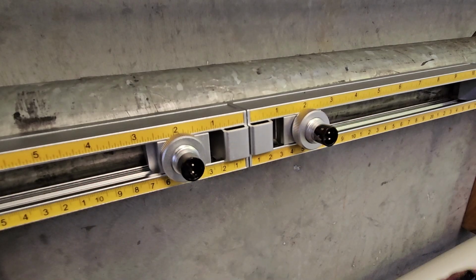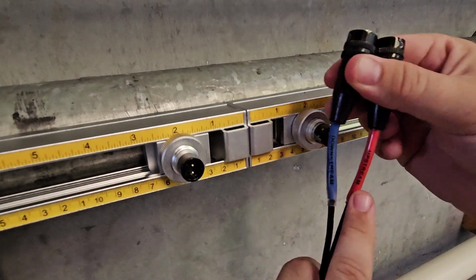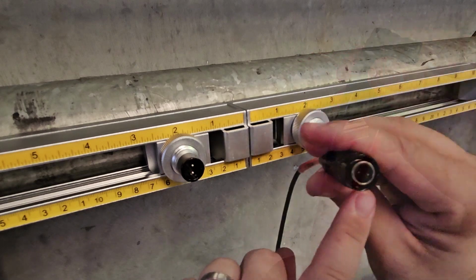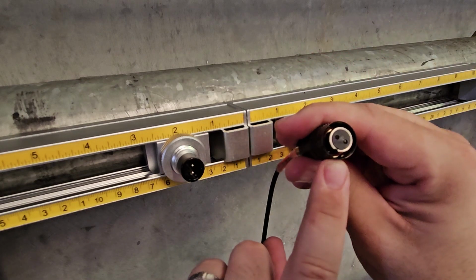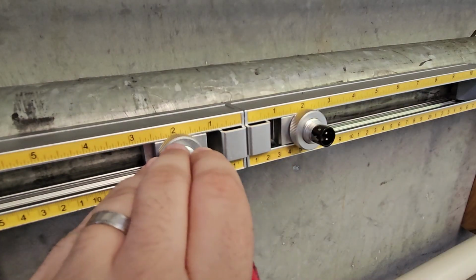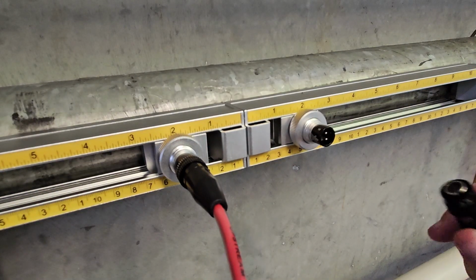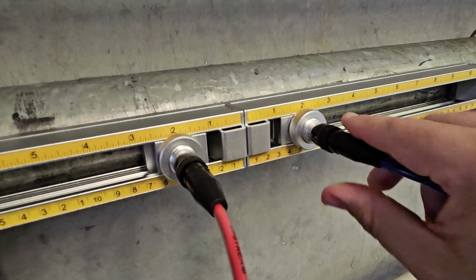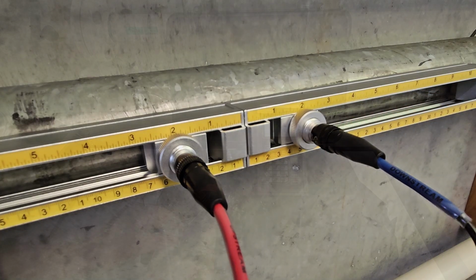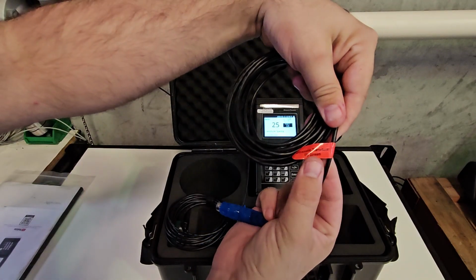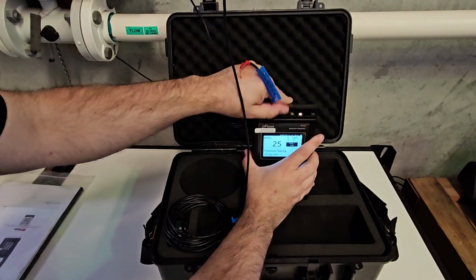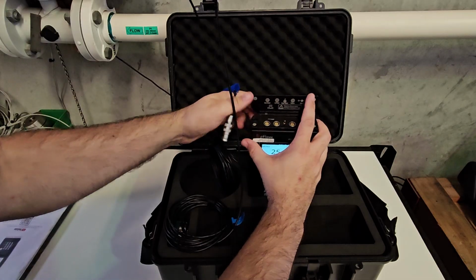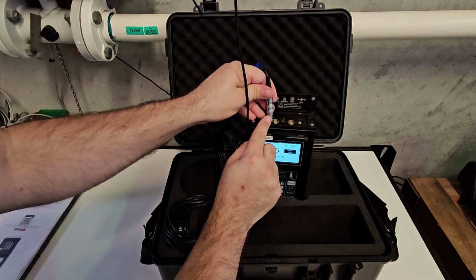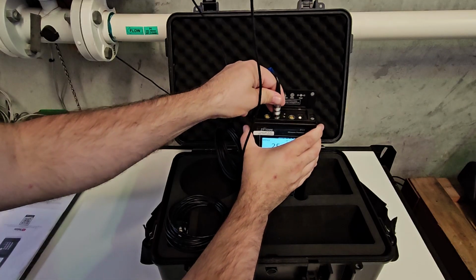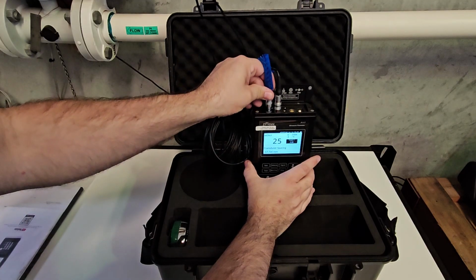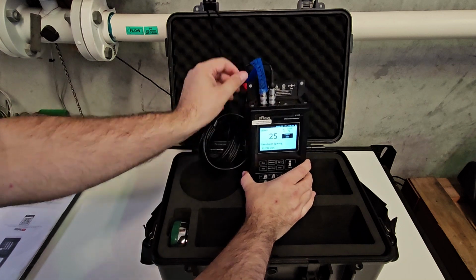Now take your sensor cables and observe which is upstream and downstream. Take the upstream cable, and also notice it has a notch in the connector and sensor, so it can only be installed in one position. Connect and push in the cable. Then do the same for the downstream sensor. At the other end of the cables, check the labels again. First I have my upstream sensor, and I will plug it into the meter's upstream port. Be aware the connector has a red dot, and this should face towards you to plug in. Then do the same for the downstream cable. It's important the cables and sensors are in the correct position, or the meter will not measure flow.